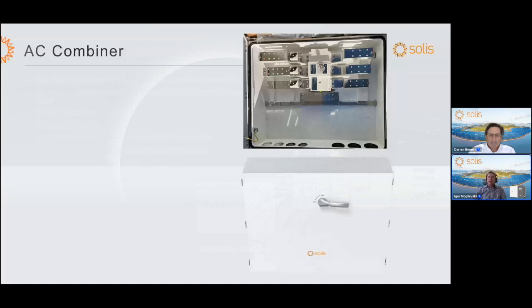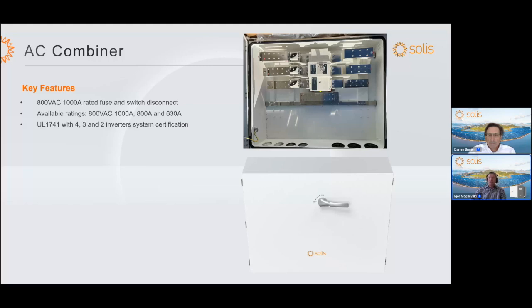With this solution, we also provide an AC combiner, which combines multiple inverters' AC output to a single combined output. So it's basically 800 volts AC, 1000 amp rated output. The disconnect comes with 3 different fuse ratings: 1000 amp, 800 amp, and 630 amp. It's UL 1741 rated and certified with 4, 3, and 2 inverter system. 90-degree ratings for the terminals. So basically the wire, when you select per NEC, it's 90-degree terminal rating.